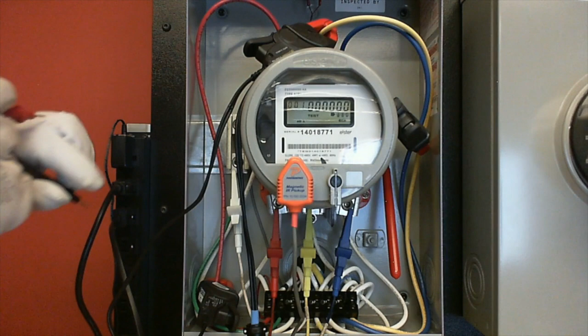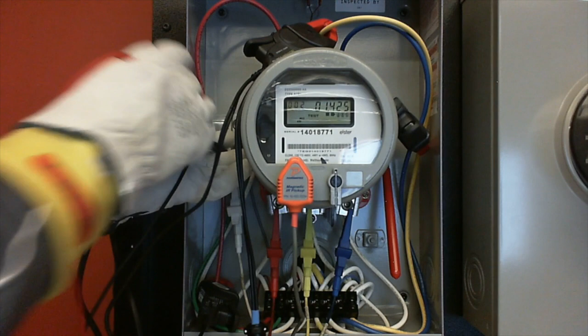So I'm going to do the same thing. I could actually get my voltmeter out and measure voltage and make sure I've got my voltage down there. Y'all want to do it? Let's just do it real quick. Same thing. We're going to go to our neutral. All right. I'm going to go to B phase, and I have nothing on my voltmeter. I'm going to go to C phase. I've got 120 volts. So I can actually go phase to phase. I have 120 volts phase to phase.